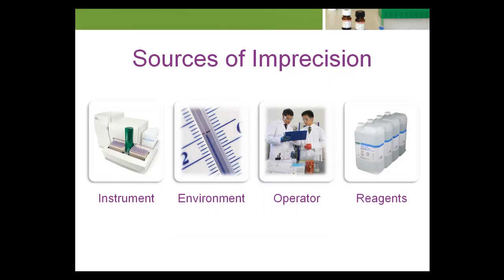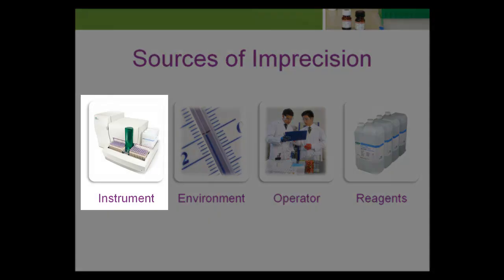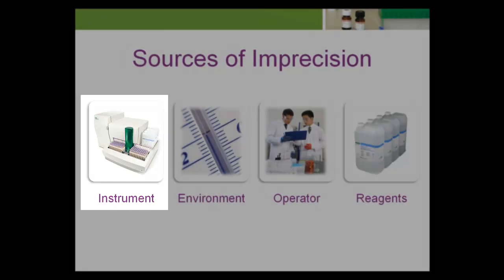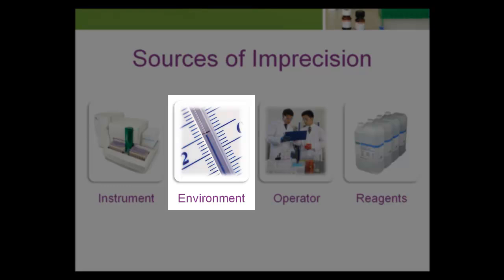Several sources can contribute to imprecision in a testing system. The age of the instrument, number of tests it's produced over its lifetime, and the number of hardware and/or software changes can all have an adverse effect on imprecision. The computerized components of modern laboratory equipment can be sensitive to environmental changes like temperature, electrical power surges, and humidity.